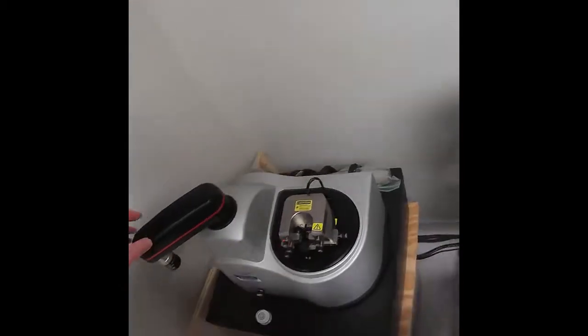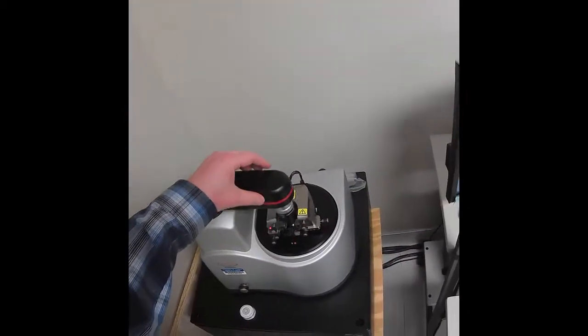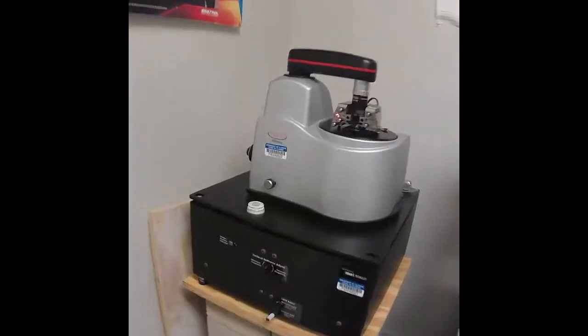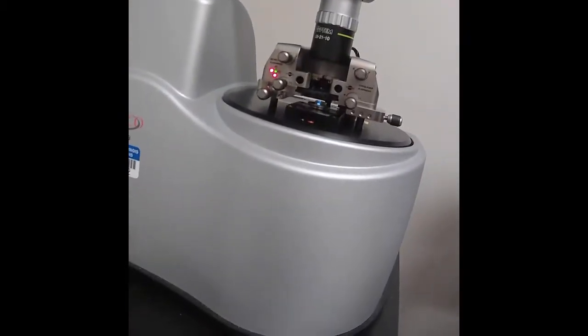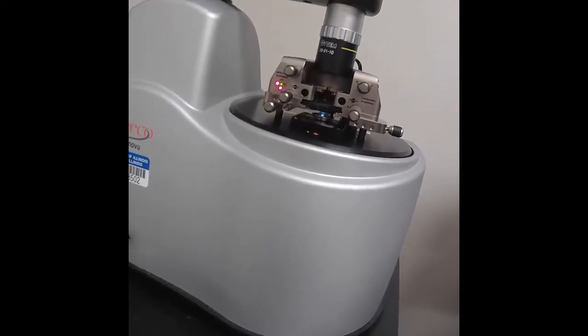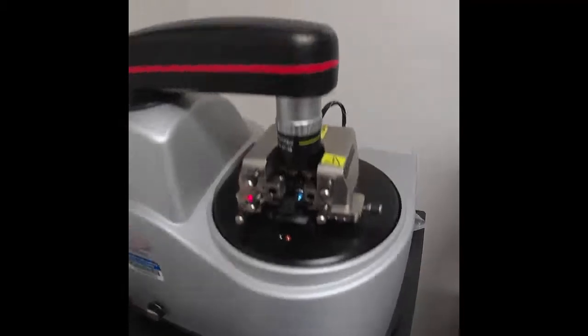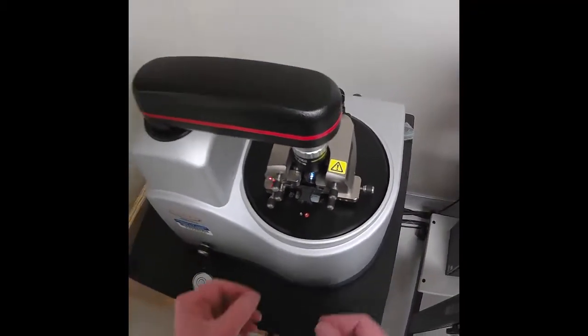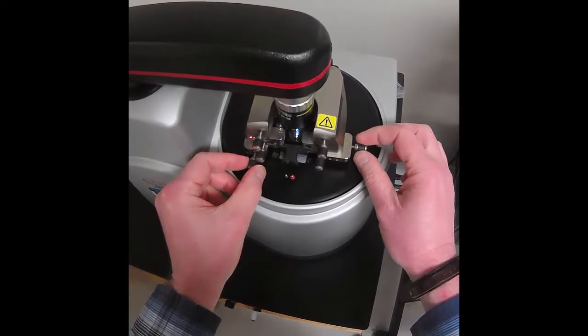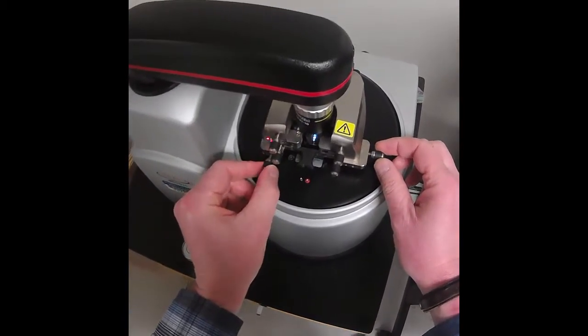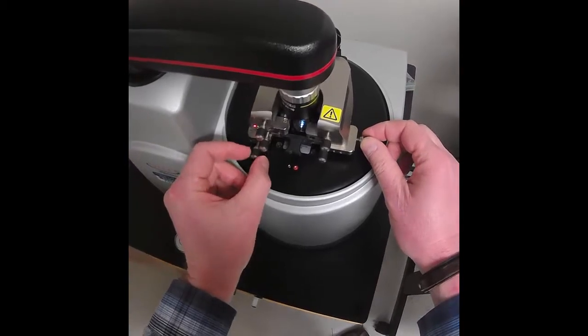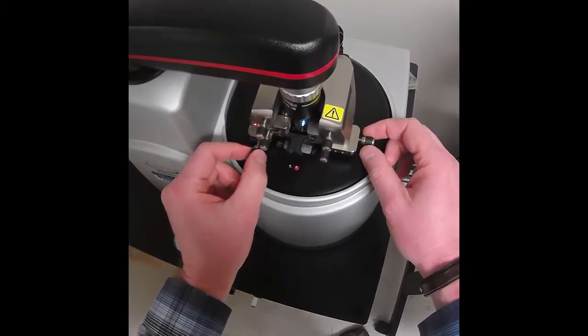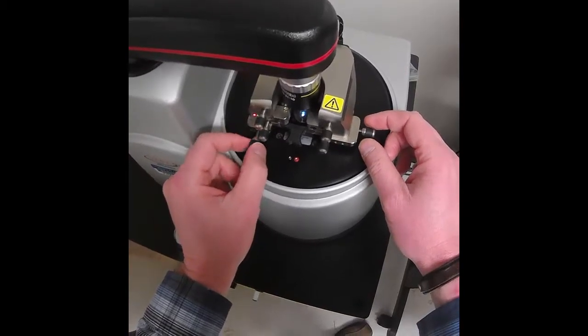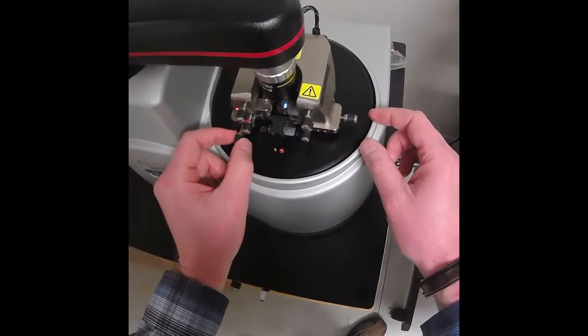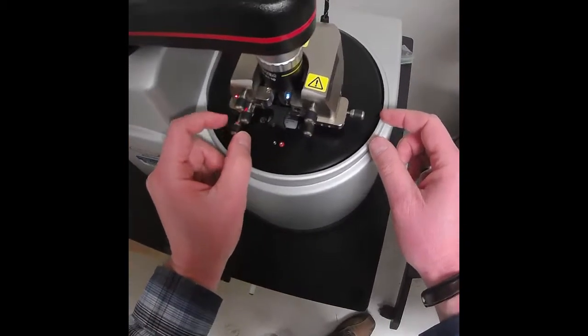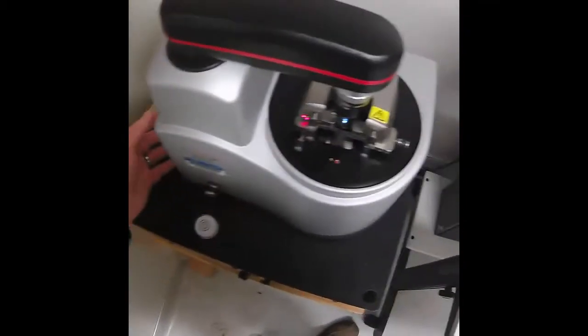So do that gently. Bring the optical boom over so we can see the probe and the sample, and you can see the probe is close to the sample surface, and it's right on the edge of the sample, so we can move the probe with respect to the sample with these knobs here. This moves it right and left, this moves it front and back. So we want to try to go back so that we're over the sample. If need be, we can remove the scanner head and readjust the sample position to make sure that the probe is over the sample. Looks like we moved that.